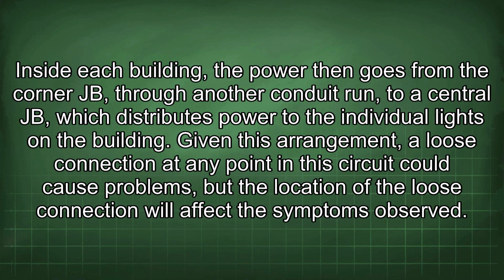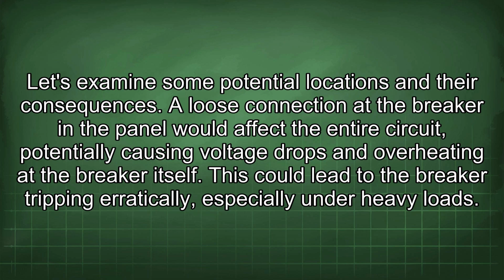Given this arrangement, a loose connection at any point in this circuit could cause problems, but the location of the loose connection will affect the symptoms observed. Let's examine some potential locations and their consequences. A loose connection at the breaker in the panel would affect the entire circuit, potentially causing voltage drops and overheating at the breaker itself. This could lead to the breaker tripping erratically, especially under heavy loads.